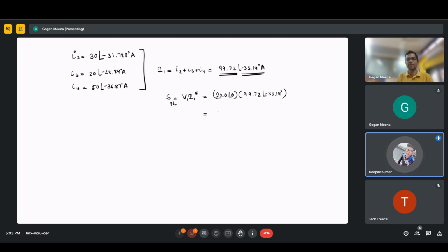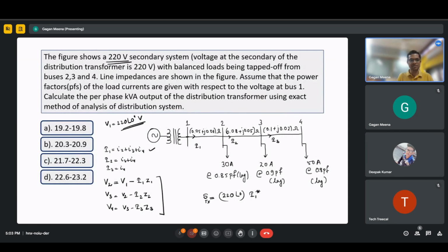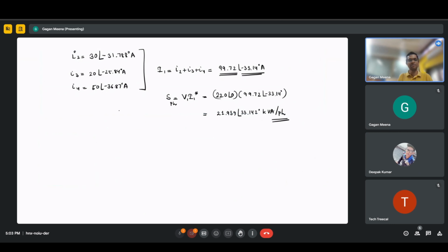So it is coming to 21,938.39 angle 33.14. Correct, so this is per phase. For three phase, you multiply it by three. But they are asking only per phase, so we need only this value, which will be the per phase kVA output of the transformer.